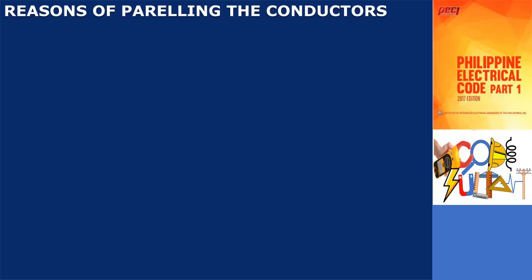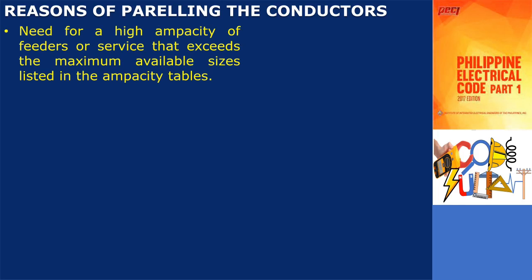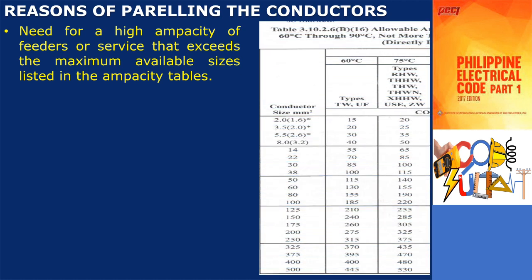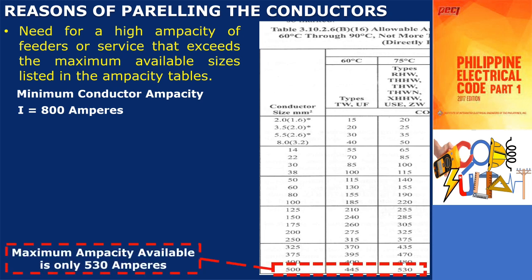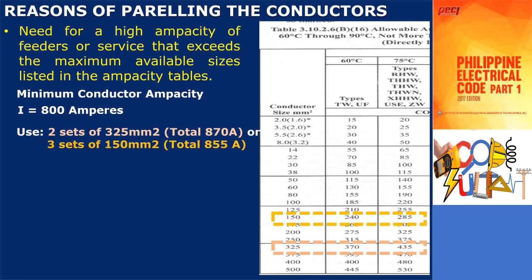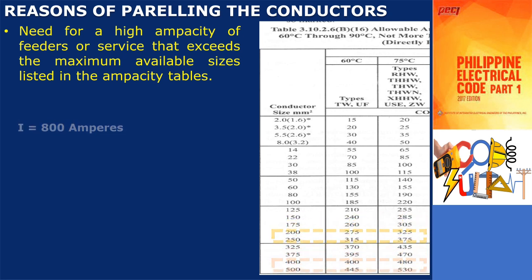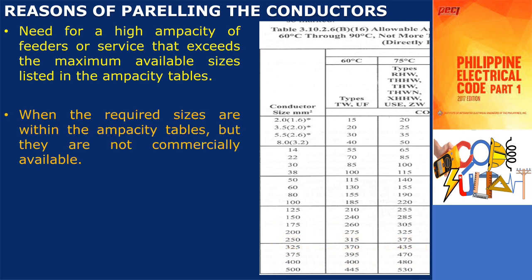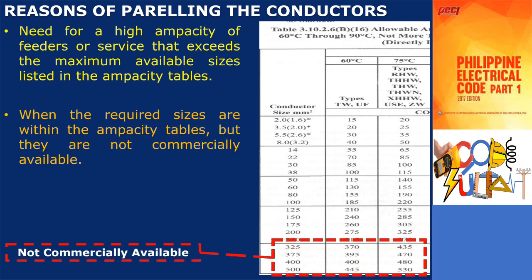There are several reasons for paralleling conductors in electrical installations. One of the main reasons is when there is a need for a high ampacity of feeders or service that exceeds the maximum available sizes listed in the ampacity tables. In such cases, paralleling multiple conductors allows for the combined ampacity to meet the required capacity. Another reason for paralleling conductors is when the required sizes are within the ampacity tables but are not commercially available. By paralleling smaller conductors, the desired ampacity can be achieved effectively.